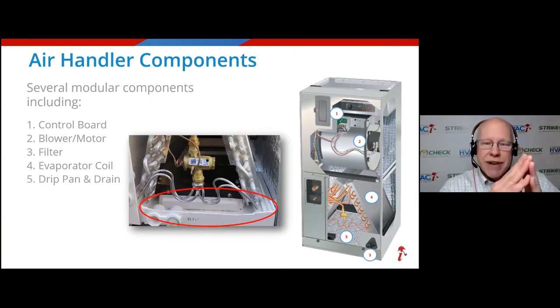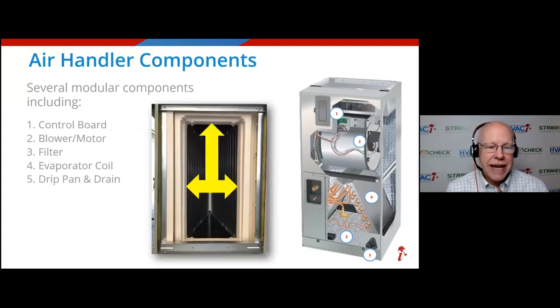We're in a warm, moist environment and we have a cold metal device, which is the evaporator coil. We're going to have condensation. We drain it into this drip pan and we drain it off. Some people don't understand that the drip pan is not very big. It's not a whole pan because you have to send air through that evaporator coil. It's just around the outside. It's a U-shape. It's not very big. It's trying to collect all that water.